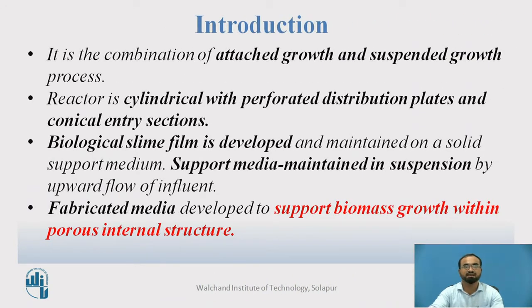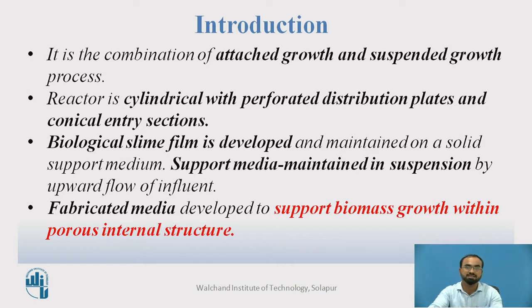Fluidized beds are basically a kind of beds which can be used in aerobic, anoxic, or anaerobic digesters. It depends on whether we are providing oxygen to it or not. Basically it is a combination of attached growth and suspended process in which the reactor is cylindrical and having perforations by which the water can come in. There is a proper conical entry section by which water can come in. It is also having a biological slim film which is developed and maintained on solid support medium. This solid support medium can be a type of particulates, typically called bioparticles, in which the microorganisms can grow.